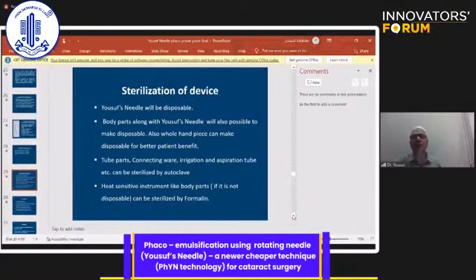Sterilization of the device: most of the handpiece will be disposable, but we have an option of sterilization. The tube parts, connecting wire, and irrigation and aspiration tube can be sterilized by autoclave. Heat-sensitive instruments like the body parts can be sterilized by formalin. The body part along with the YOUSUF needle can also be made disposable. The whole handpiece can also be made disposable for better patient benefit.